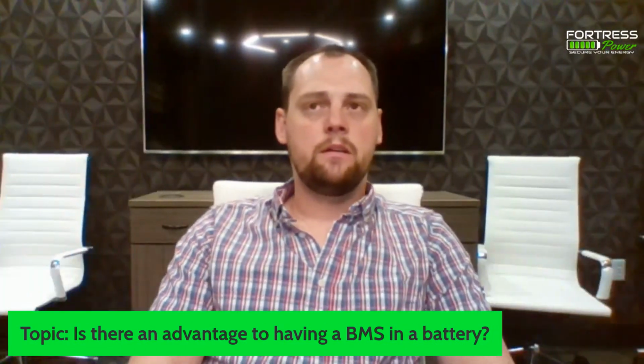Well, there's the manufacturer's defined depth of discharge, and then there's realistic depth of discharge. I've been selling lithium batteries for about five years now, so I'm about halfway through what manufacturers say is the usable life of a lithium battery. I have yet to have a customer come back to me with a situation where a battery has failed—it's still functional, but failed prematurely of its cycle life. On the other hand, with lead acid batteries, their cycle lives are highly dependent on use and abuse, and any use is abuse. The amount of use really is the scale of that abuse.